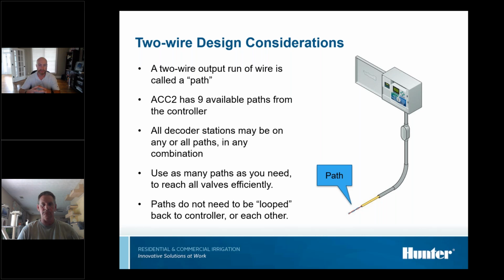So what you really need to consider is, how do I reach all of my valves most efficiently? And then we'll talk a little bit more about this in a second, but how do I also isolate this system into sections so I can ease troubleshooting in the future? So another important thing to realize is you don't need to loop paths together. So when you get to the end of the path, it's the last decoder, that's where the 2-wire path terminates. No need to loop it back around to another path or cross it, anything like that. You just need to end it right at the end of the last decoder.